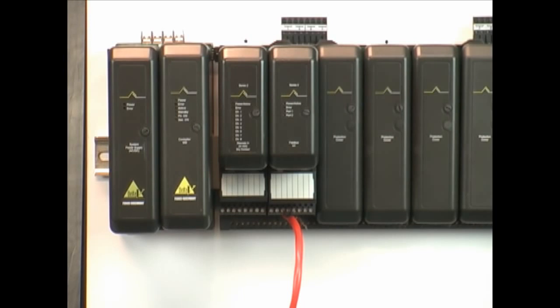It's independent of manufacturer, but the host is where all of your control will be done. And this is where the LAS or the Link Active Scheduler is housed, which controls the schedule for the rest of the field bus network.